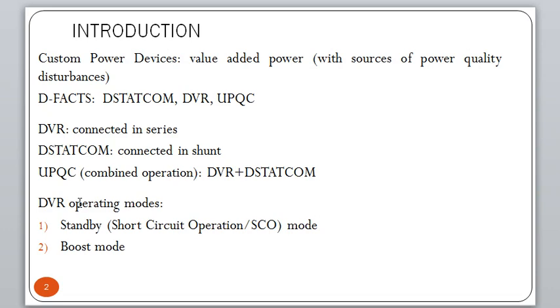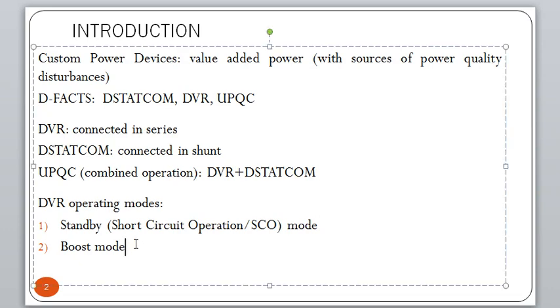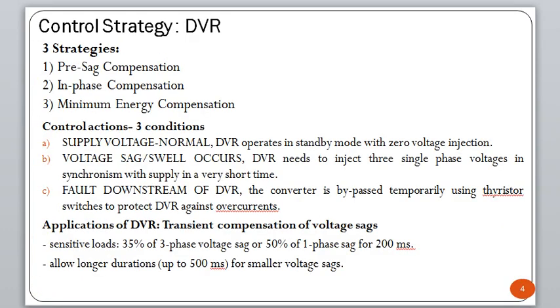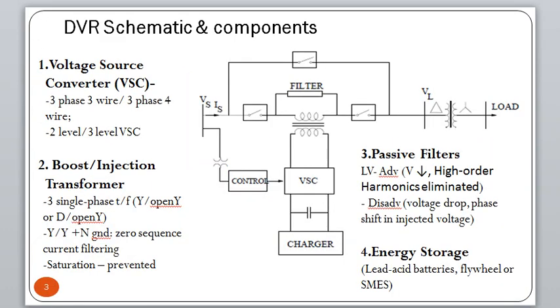DVR can operate in two modes: standby mode or boost mode. Standby mode is also called short circuit operation (SCO) mode. In standby mode, there is no injection of power and no compensation is provided to the system; if there is a battery, it can charge the battery. In boost mode, the DVR injects energy into the system in the form of voltage.